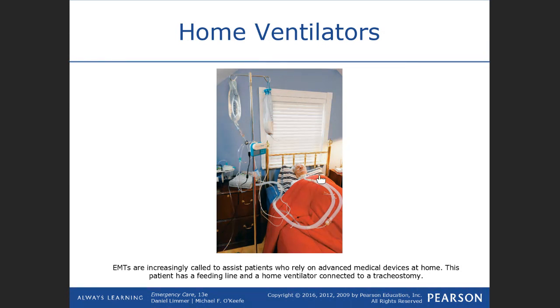If the alarm starts going off and the device doesn't appear to be working, one of about four things can be happening. For one thing, the tube dislodged. It fell off the tracheostomy site for whatever reason. If that happens, the machine is going to sense that lack of resistance, and it's going to send off the bells and whistles. So that's the first thing you should look for. Did this thing pop off? And if it did, just pop it back on.